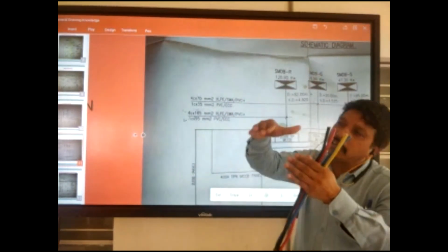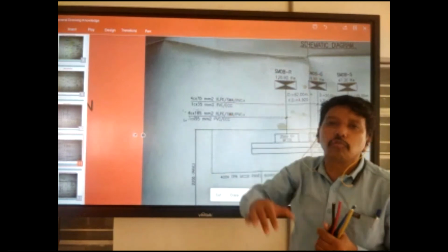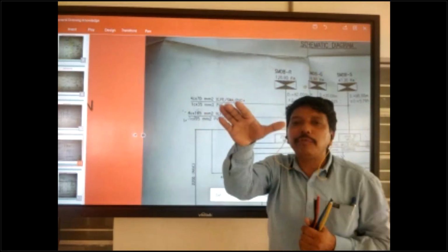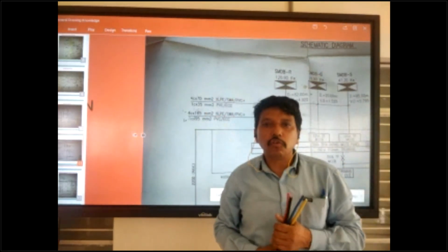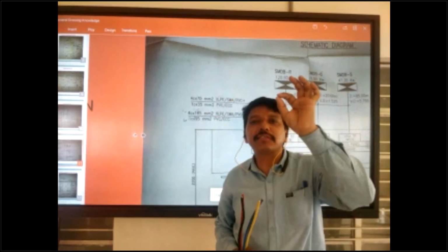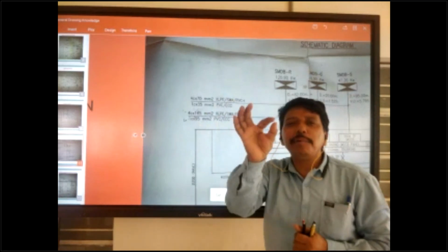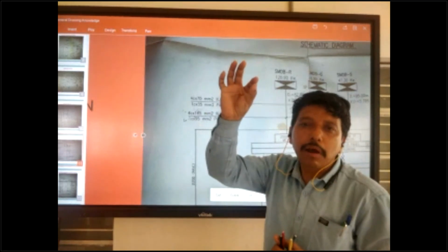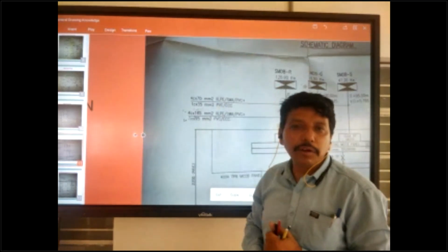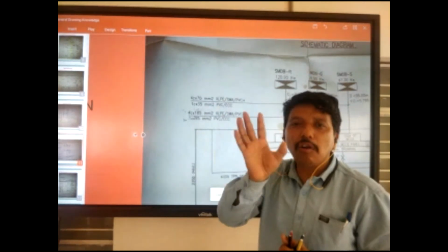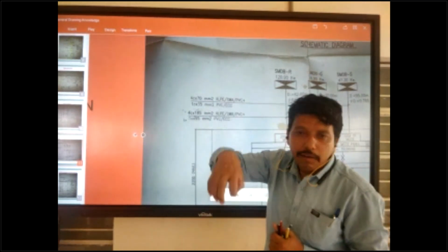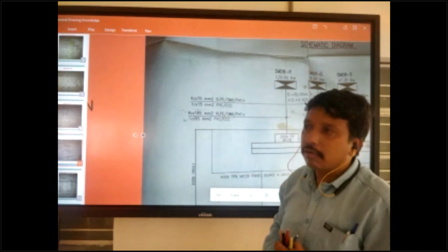You can use a little bit higher, this is not an issue, but going below half value is not allowed. Sometimes the same half value cable is not available. At that time we can use a little bit higher than half value of the cable, okay? Never use below half value cable.